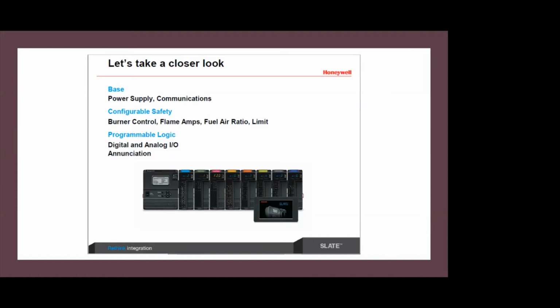Any way you've configured this system, we can get all of that data out and available to the end user. So you've heard us say this several times now: configurable safety and programmable logic. Configurable safety is the part that holds all of the safety approvals - it consists of the burner control module, the flame amp module, the fuel air ratio control, and the limit module. That's the safety part of the system, which we can configure from the base module, as well as our display that we saw earlier.